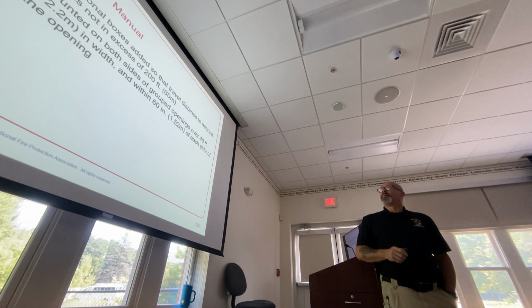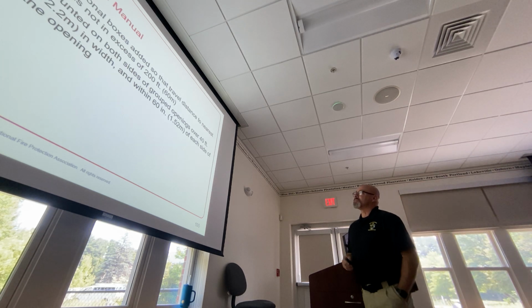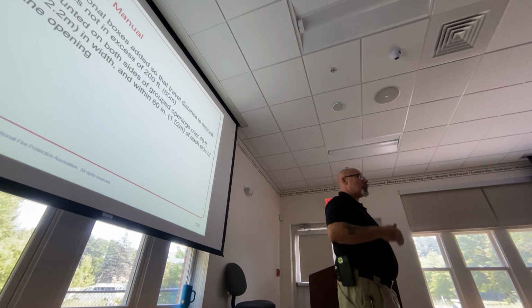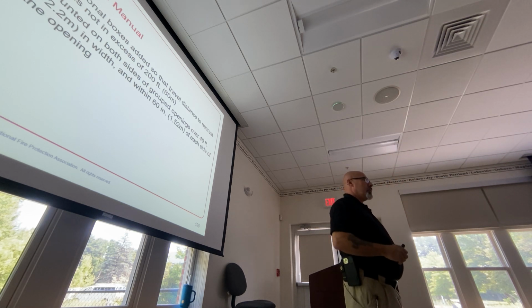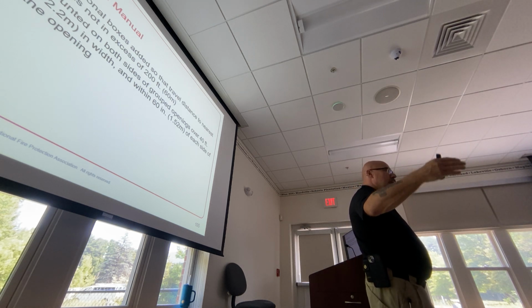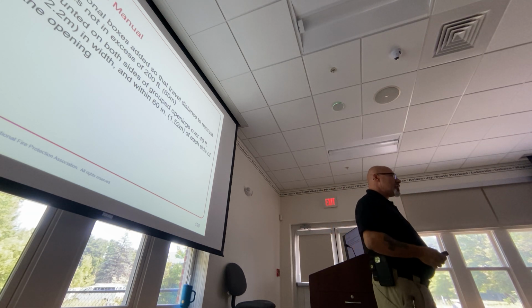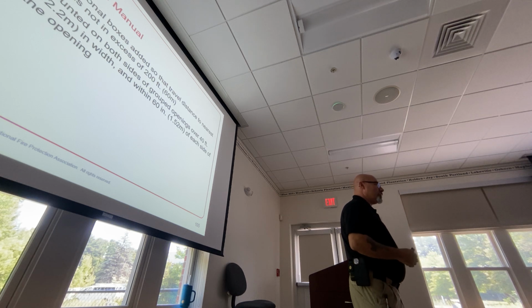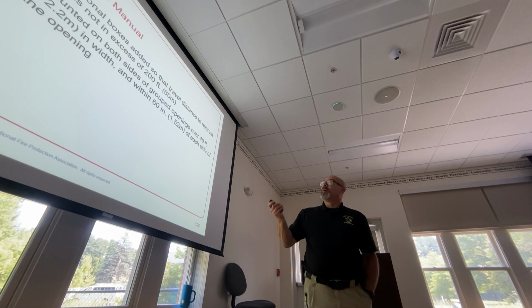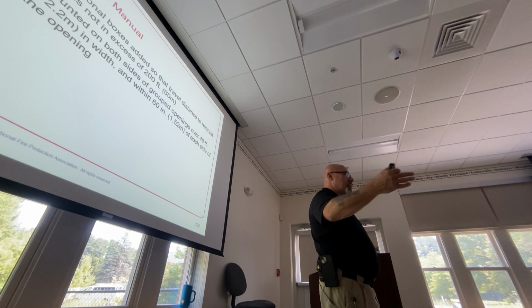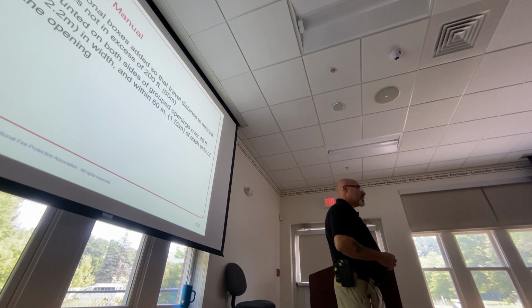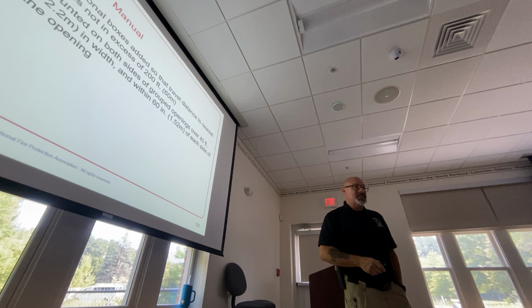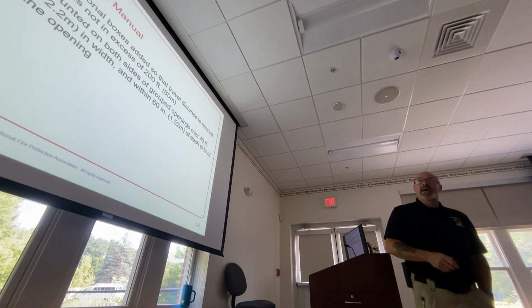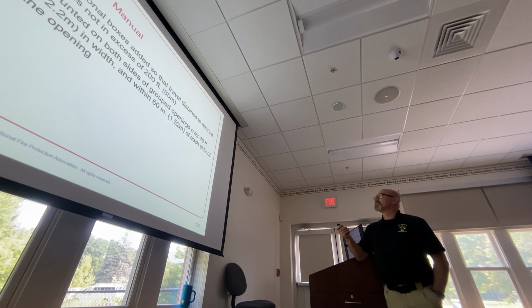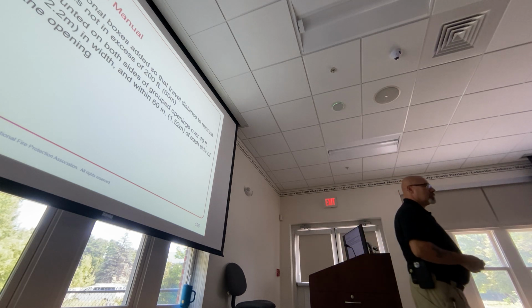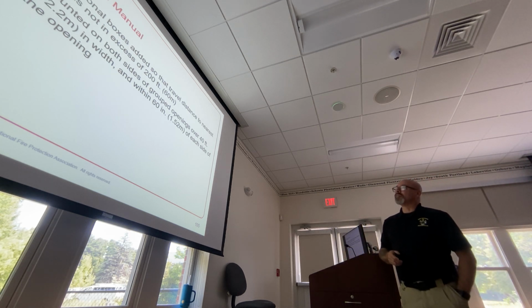Additional boxes are added so that the travel distance to the nearest box is not in excess of 200 feet. This is in relation to a corridor, or travel distance. If I have to travel more than 200 feet in a building without having access to a manual pull station, I have to put one in prior to that 200 feet or right at the 200-foot mark. So if I have a corridor or travel distance that is 210 feet, is it okay for me to have just that one manual box? No, because if we're in excess of 200 feet, then I need to add an additional box. I actually have a practice question on this that you will look up. I don't think we'll be able to practice it in class today, but I will send that to you.